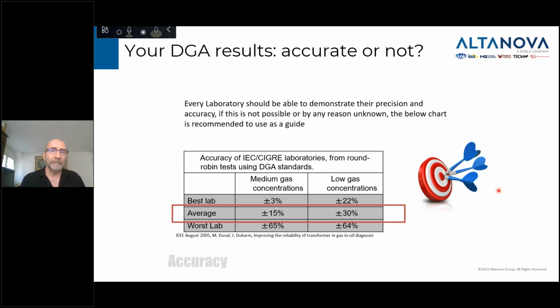One of the samples had what we call medium gas concentration, so it's mostly around 100 ppm. And one of the samples had low gas concentration, around 10 ppm. They asked those labs to measure them and send back the results. Then they compared the result they got from the lab versus the sample that was sent. And what you see here is the results. The best lab for the medium gas concentration measured it to plus or minus 3%. It was incredibly good. And for the low gas concentration it was plus or minus 22%. That could be expected, considering when you get to 10 ppm, a very small error, just missing 1 ppm, is an impact of 10%. The average lab for the medium gas concentration was plus or minus 15%.